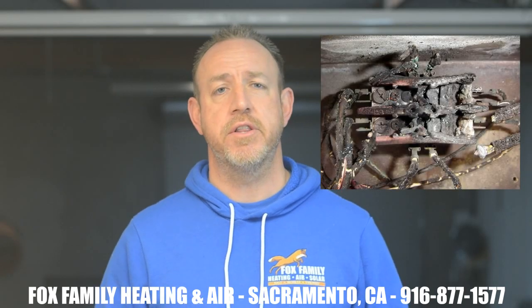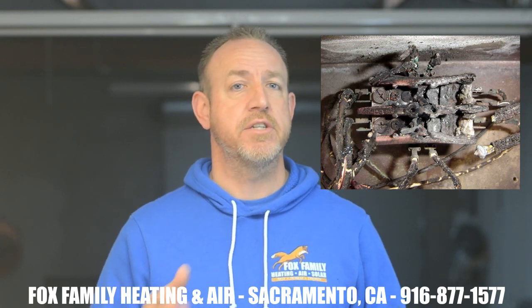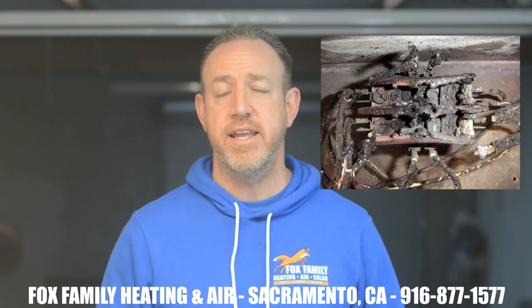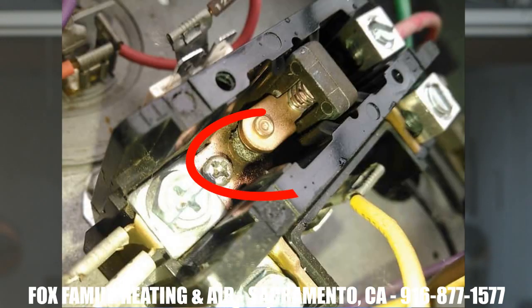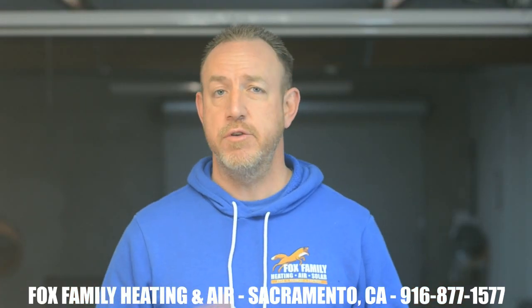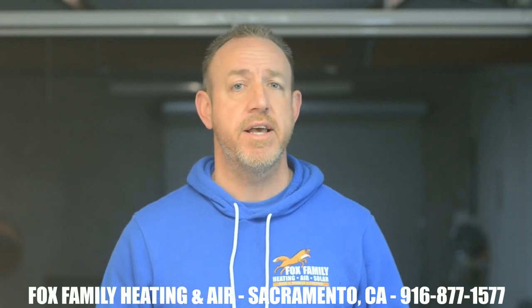Relays and switches can stick, burn, and pit. Just like a contactor on the condenser outside, the control board at the furnace has miniature relays that allow certain motors to receive the voltage they need to operate. And just like the contactor on the condenser, those furnace relays start to pit and burn from arcing that occurs across the contacts as they close. High temperatures can melt the protective coating on the windings of the coil of a relay, which can prevent the contacts from closing in the first place.